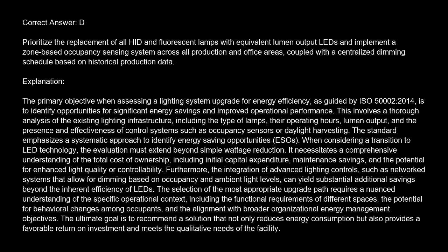This involves a thorough analysis of the existing lighting infrastructure, including the type of lamps, their operating hours, lumen output, and the presence and effectiveness of control systems such as occupancy sensors or daylight harvesting. The standard emphasizes a systematic approach to identify energy-saving opportunities (ESOs). When considering a transition to LED technology, the evaluation must extend beyond simple wattage reduction; it necessitates a comprehensive understanding of the total cost of ownership, including initial capital expenditure and maintenance savings.